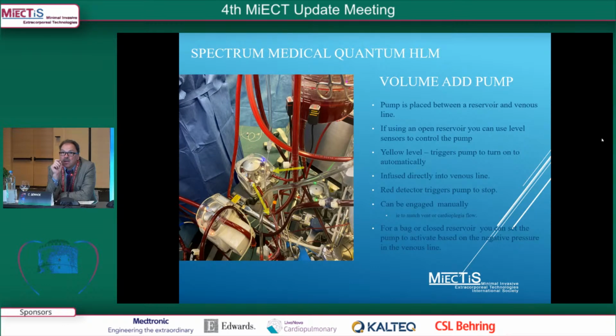And if the level hits the red sensor, then it will automatically turn that pump off, so you have no risk of entraining air into the venous line.